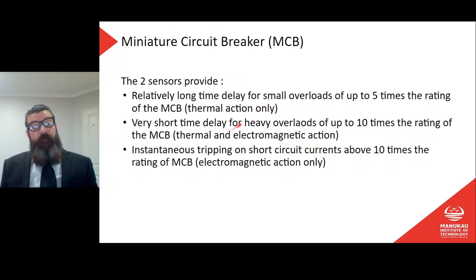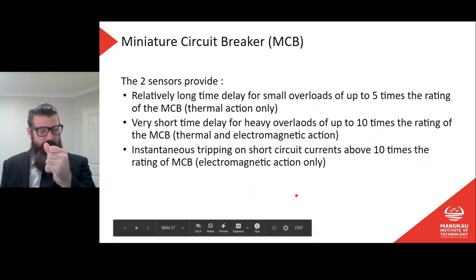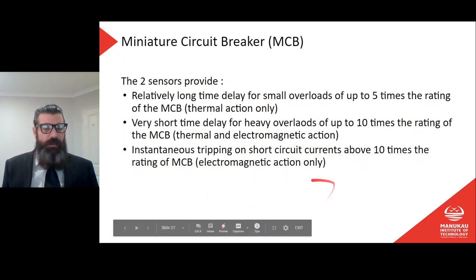So our two sensors provide a fairly long time delay for small overloads, up to 5 times the rating of the MCB. Very short time delay for heavy overloads, 10 times the rating. So that's our electromagnetic and thermal. And instantaneous tripping for short circuit currents above 10 times. So up to 5 times, pretty slow, and that's working on the thermal action. Up to 10 times, it's happening pretty fast, and that's the thermal and or the electromagnetic part of the MCB. And then over 10 times, it's going to happen just like that, fast. So that's our short circuit, right? And that's the electromagnetic action.